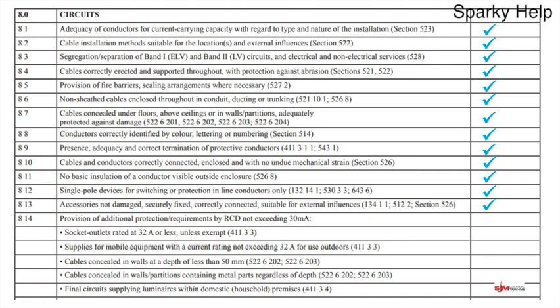Back to item 8.14 — where you've actually got RCDs and what circuits they're on. Chances are it's going to be sockets, you may have equipment or sockets for outdoors so that will be RCD'd. You may have cables in the wall but might not have metal structure within the wall so that wouldn't need worrying about. You'll probably have an RCD on your domestic lighting too, so that will be a tick.